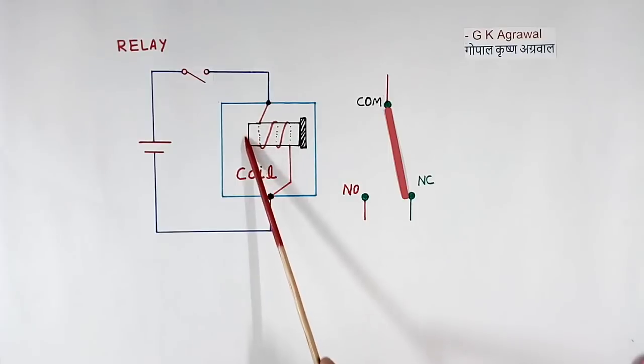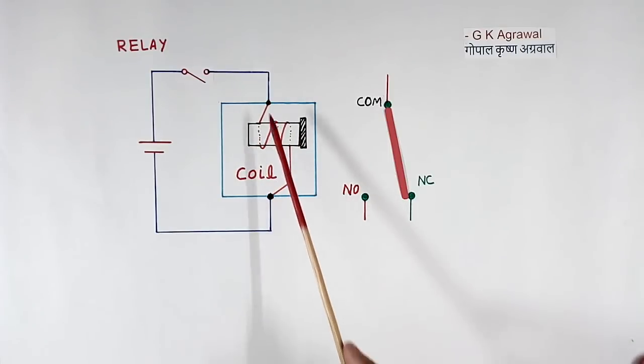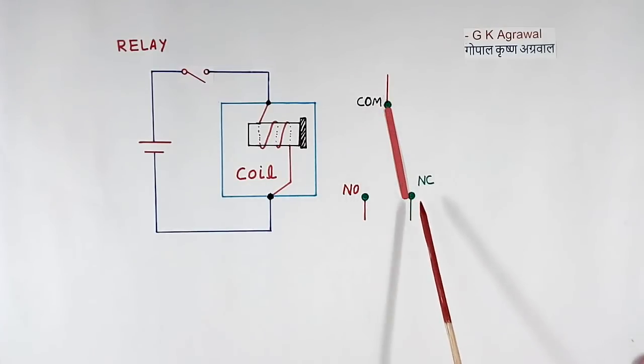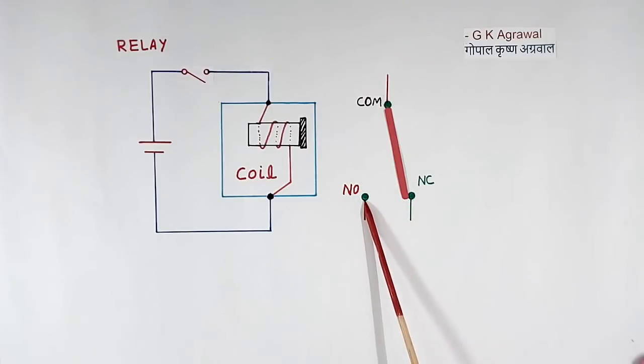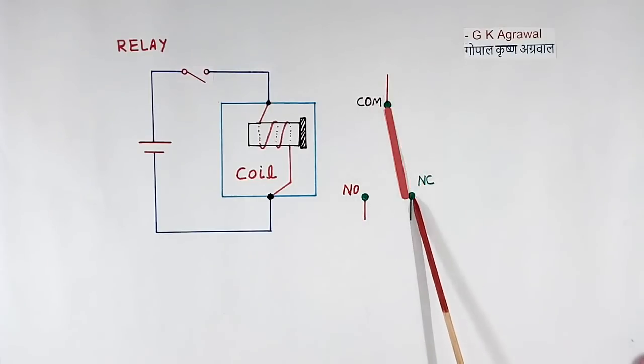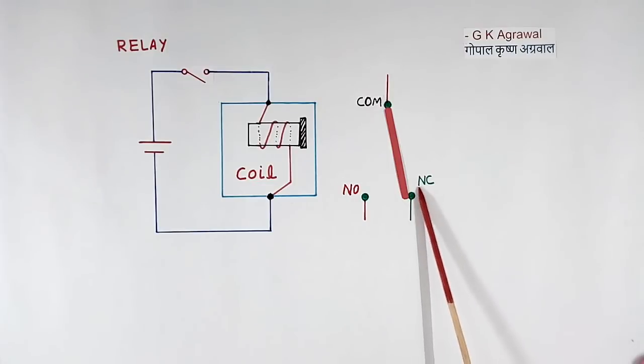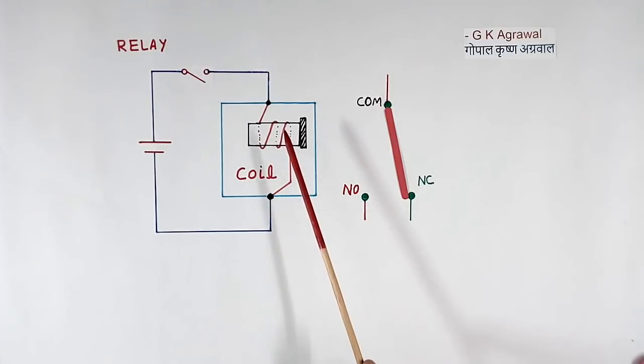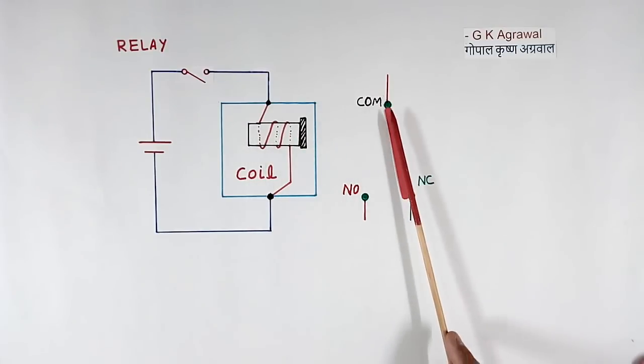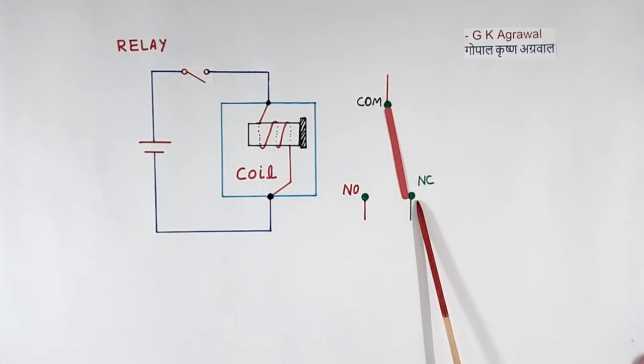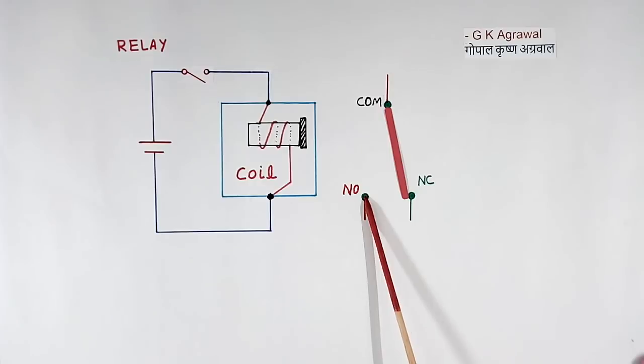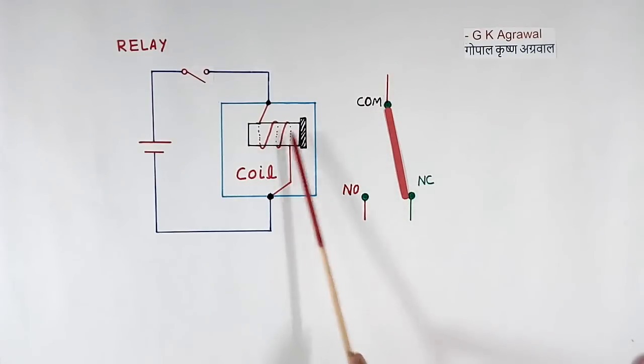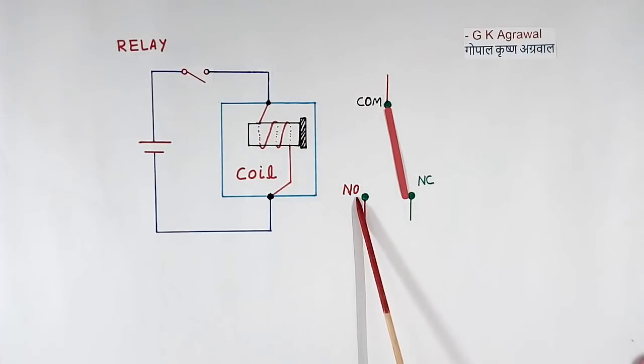In the relay there is a coil with two terminals — one here and one here — and one contact which has three terminals: one common, one NC (normally closed), and one NO (normally open). The NC contact is normally closed because when current is not available, this contact is closed. The NO contact is normally open — when current is not available it is open, and when current flows it closes. So this is NO and this is NC.